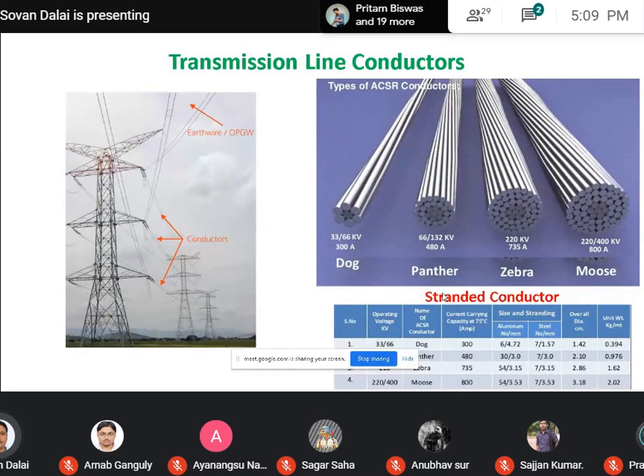Generally, two types of conductor are used in transmission. One is called the stranded conductor. A stranded conductor is basically a solid conductor that, instead of a single conductor, consists of a number of strands. Why do we use a number of subconductors inside this solid conductor? Because if we use more strands, it is better from a reliability point of view. Also, it provides much more mechanical strength compared to a single solid conductor. Here is an example of a transmission line conductor, called a stranded conductor. A stranded conductor is equivalent to a solid conductor, but it is replaced by a number of subconductors.